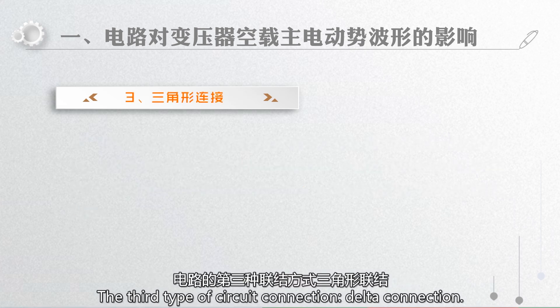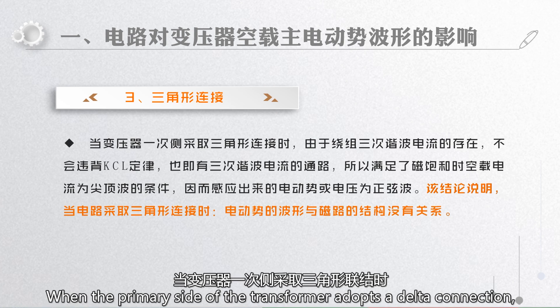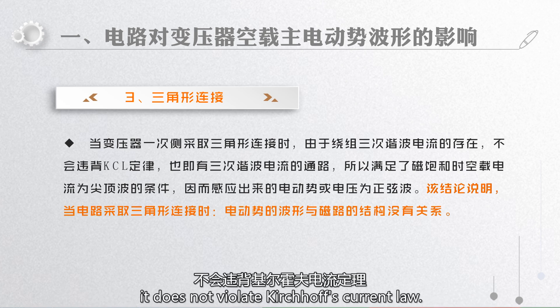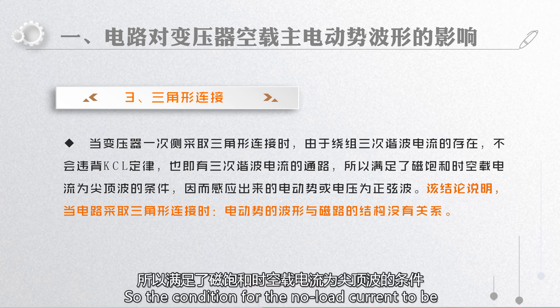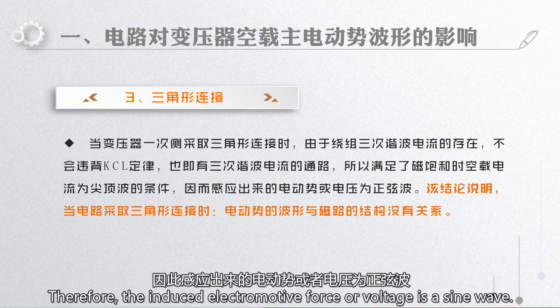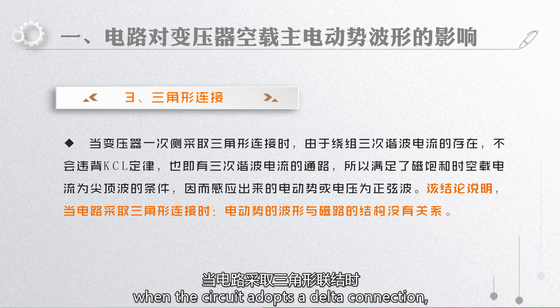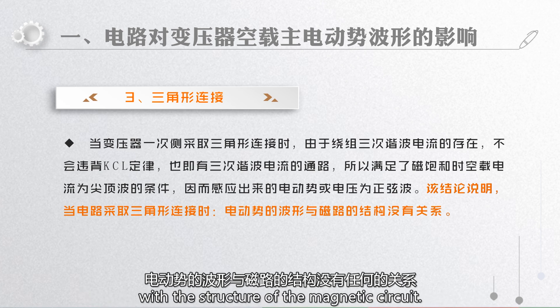The third type of circuit connection is delta connection. When the primary side of the transformer adopts a delta connection, due to the existence of the third harmonic current circulating in the winding, it does not violate Kirchhoff's current law. That is, there is a path for the third harmonic current. So, the condition for the no-load current to be a peaked wave under magnetic saturation is met. Therefore, the induced electromotive force or voltage is a sine wave. This conclusion indicates that when a circuit adopts a delta connection, the waveform of the electromotive force has nothing to do with the structure of the magnetic circuit.